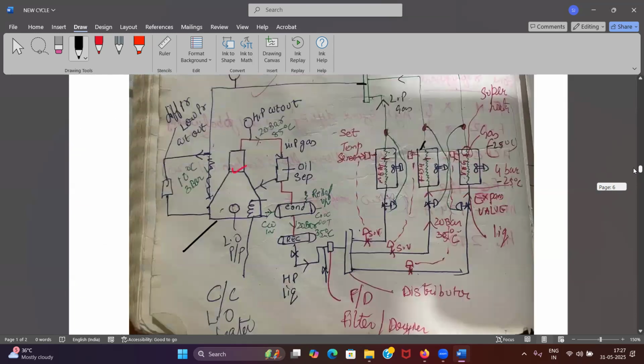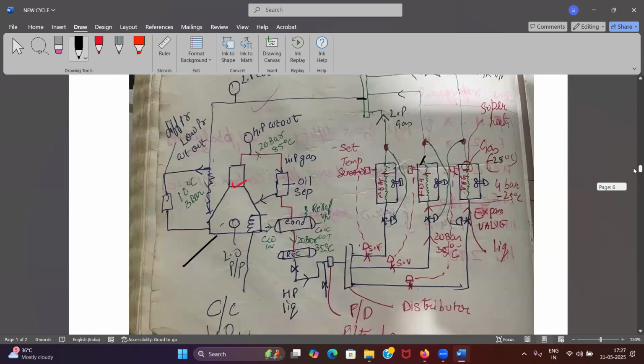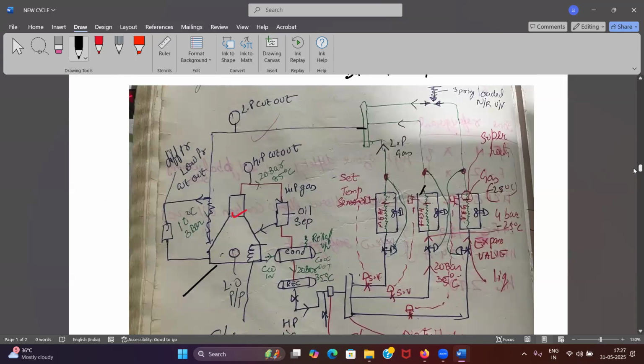Less refrigerant will come into the inlet because we need less cooling. That is the first point, obviously, and the second is that we do not want too much refrigerant to flow into my veg room. I am not going to cool my veg room according to my meat room and fish room. We wanted the maximum for the others, so for this I have set the back pressure.